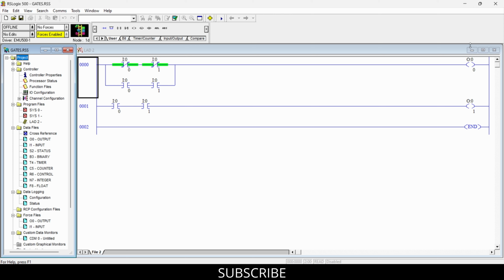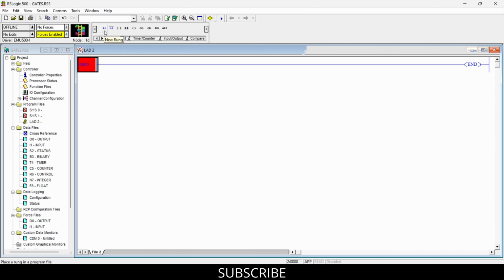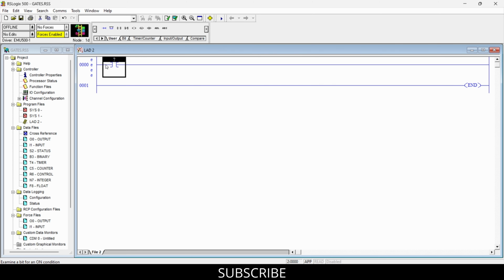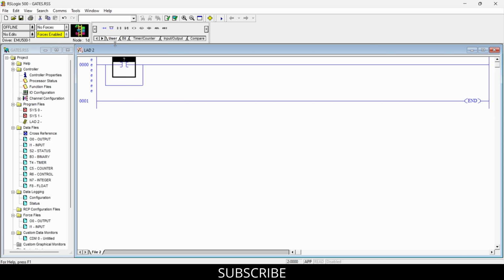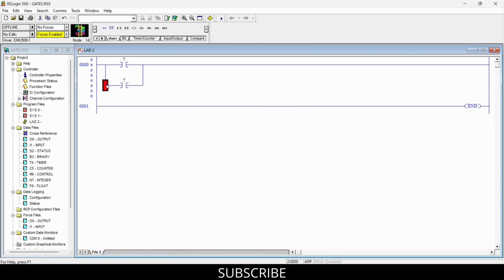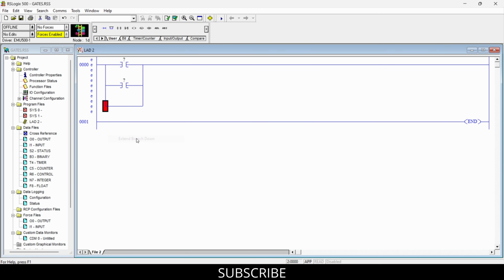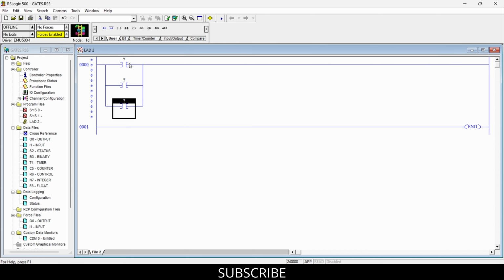So let's arrange the inputs and outputs as per the conditions. For the first condition, we need to add one rung here, add one contact, add one branch instruction, add another contact, and extend the branch down for the third input. So I have arranged three contacts in parallel because there are three processes and one output coil.